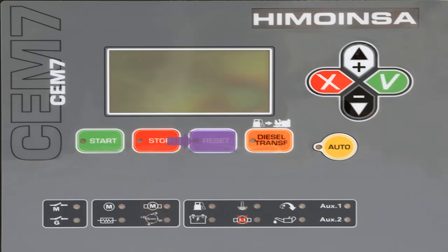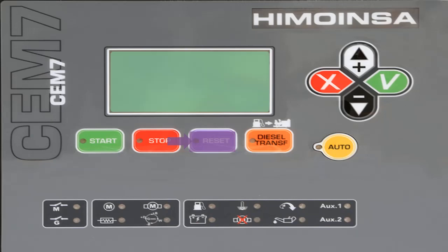The alarms reset button allows acknowledgement by the user of numerous alarms that may be present from the engine or alternator. A flashing LED means that pending notification alarms can be cleared. A lit LED means there are active alarms, which can only be cleared after the solution of the malfunction.